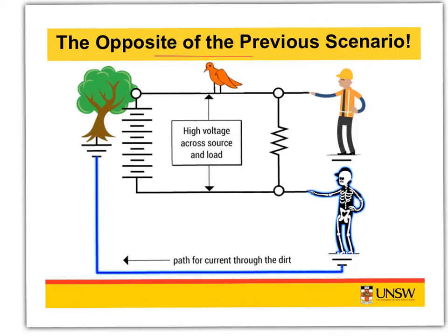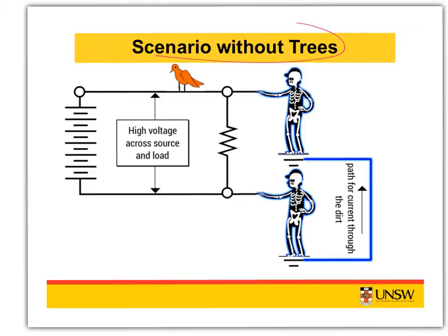Now let's go to the opposite of the previous scenario. If the tree were to brush up against the top wire in the circuit, it would make the top wire safe to touch and the bottom wire dangerous. However, tree branches are only one potential source of earth faults in a power system. Let's now consider a different scenario without the trees. Now consider an ungrounded power system. So there is no ground here.